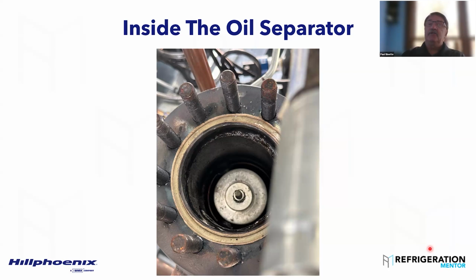So what he told me was, oh yeah, my receiver pressure went to 620. It's 620, 40 bar on a Danfoss system or Carel. That's just the HPV valve off, because all of a sudden it's saying, all right, look, I've got excessive pressure in my vessel. I'm getting close to the relief valve. I can't control it, so I need to shut this down. I can't take any more pressure.